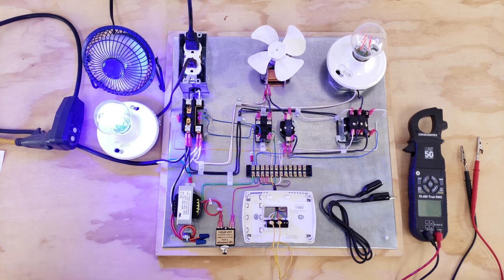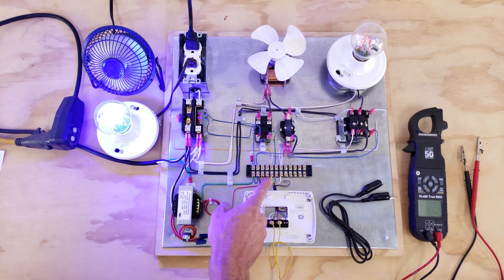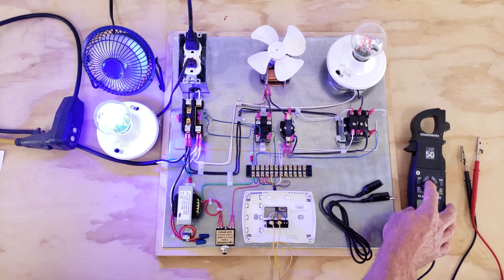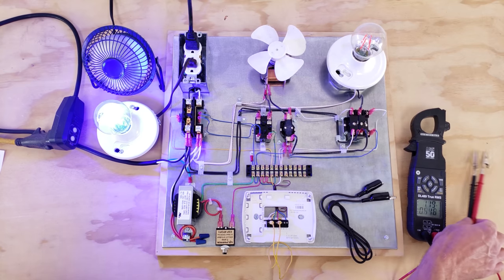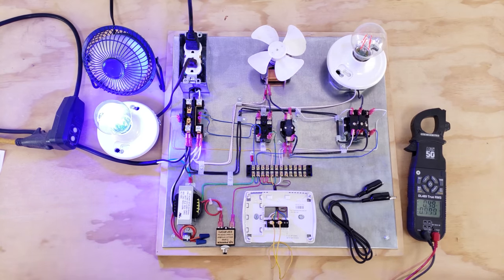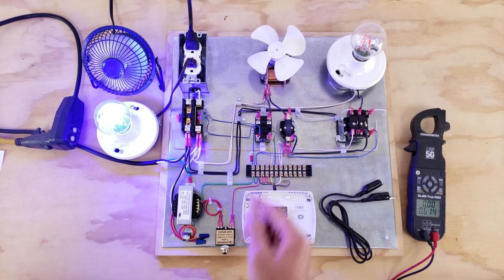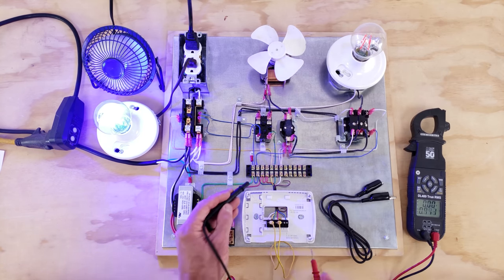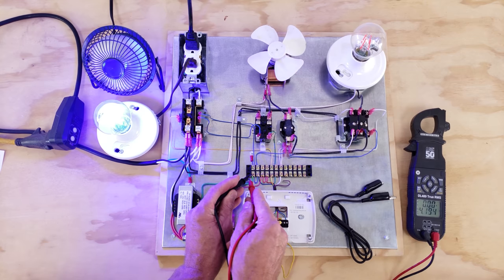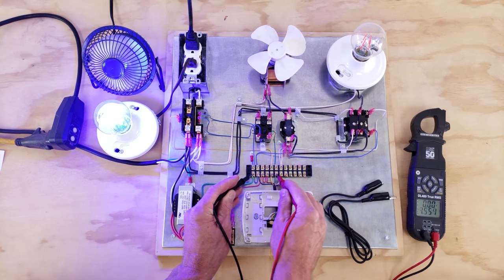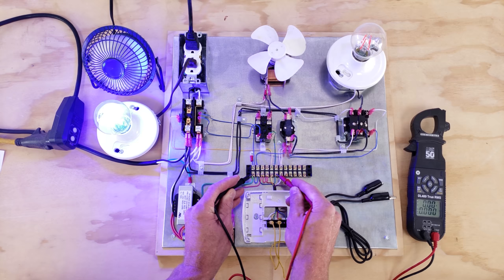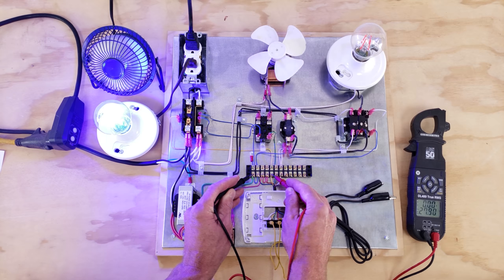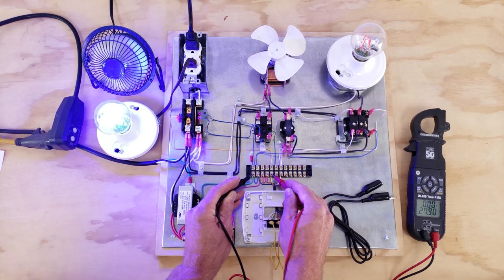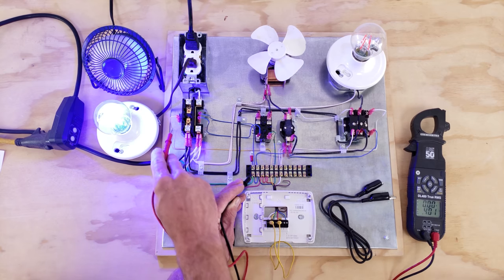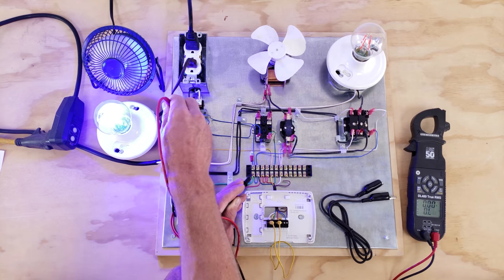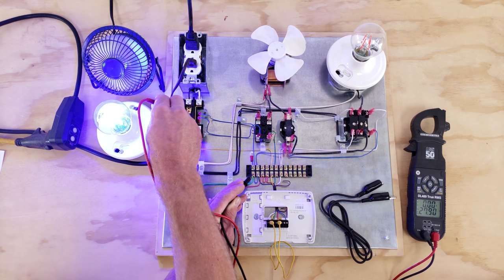But basically what's happening here is we only have this Y wire powered. So I'm going to turn our multimeter on, and we're going to take our measurements right here. If you're wondering, why is my blower motor not on right now? What you can do is place one probe right on the common, and then put one right on the G. You see you have no voltage, but when you put your probe onto the yellow wire, we have 27 volts. So you could follow that right through this whole board right here. And so we're right there, 27 volts.